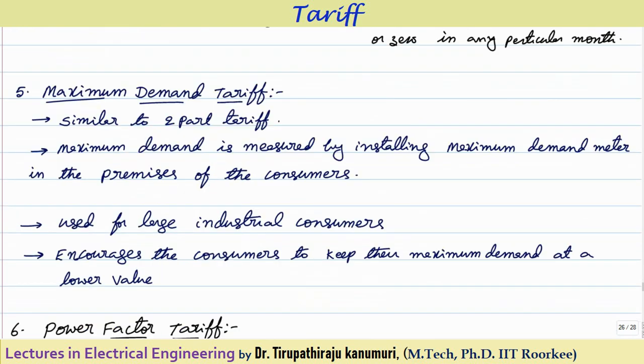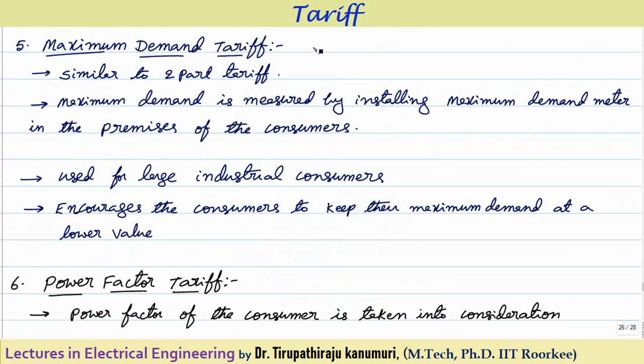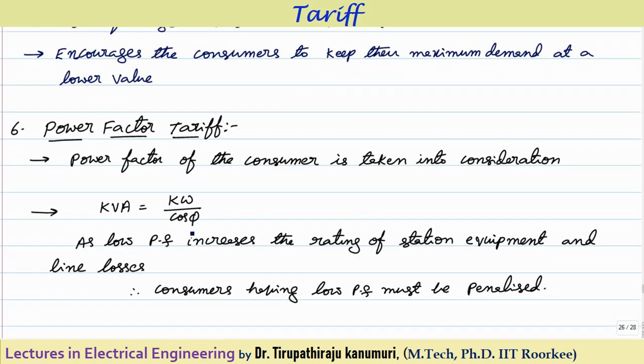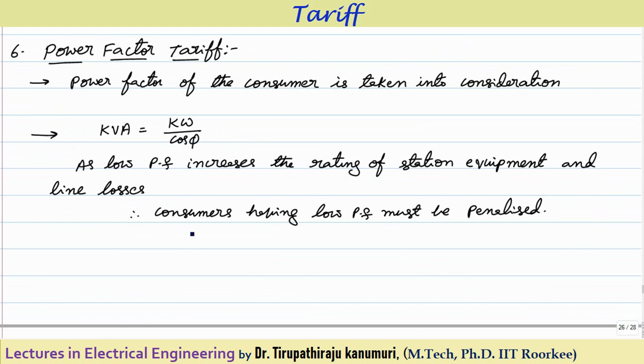The modification of this is maximum demand tariff. Here, because the maximum demand is not measured separately in two-part tariff, the consumer is paying more. If the maximum demand is measured using a separate instrument, then only if he consumes power in a particular month should he pay the bill; otherwise, the bill will not be there. This is similar to two-part tariff, but the maximum demand is measured by installing a maximum demand meter in the premises of the consumer. This is mainly used for large industrial consumers because one separate maximum demand meter is required, which increases the cost. This encourages the consumer to keep their maximum demand at a lower value — lesser the maximum demand, lesser the amount he pays. So the industry will not install very big appliances; it will install smaller equipment but try to run throughout the day so that energy charges will decrease.